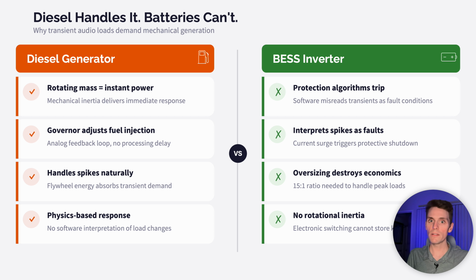And on the other hand, diesel generators handle transients just fine through physics. Rotating mass provides instant power availability while the governors catch up. There's no software interpretation, no processing delay, but inverters don't have that luxury. The protection algorithms trip on current surges, and if you try to oversize the battery system to handle those spikes, you destroy the economics entirely. It just doesn't make sense.